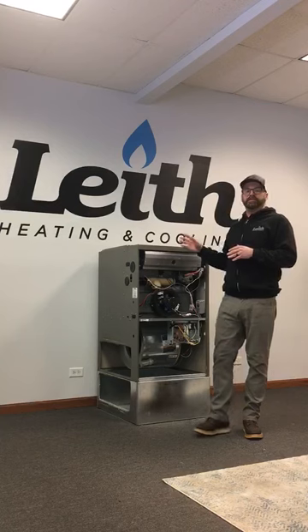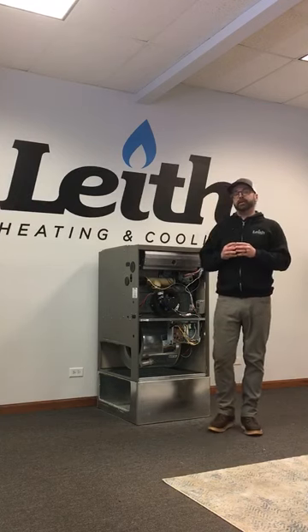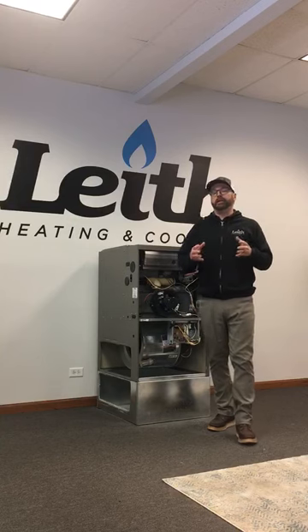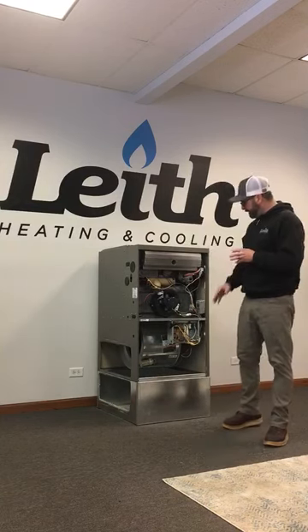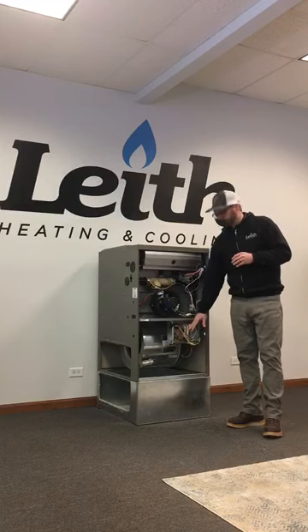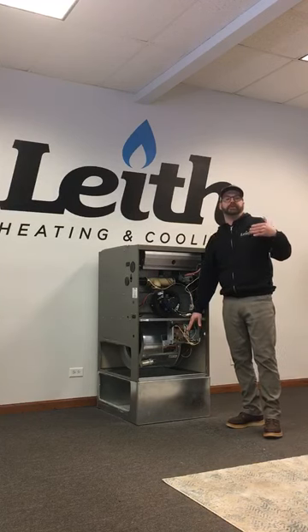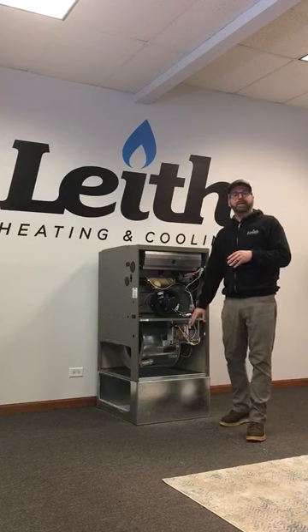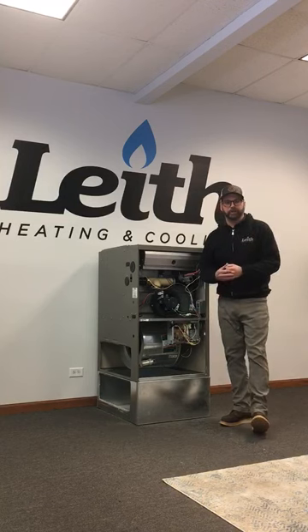Today I'd like to go over the sequence of operation of a gas-fired furnace, from the time the thermostat calls for heat to the time in which that call for heat is satisfied. When a thermostat calls for heat, it sends a signal to our ICM module. Our ICM module is also referred to as the ignition control module. It's like the brain of the operation.